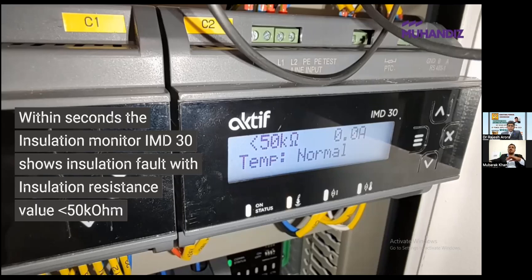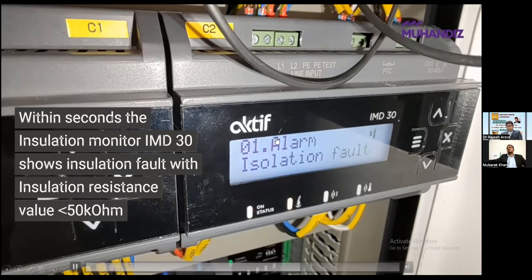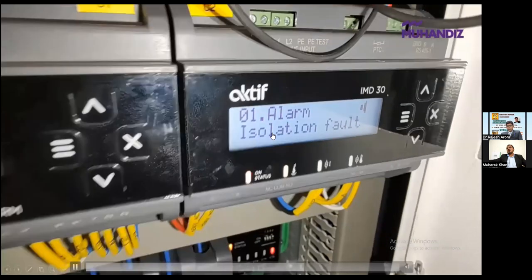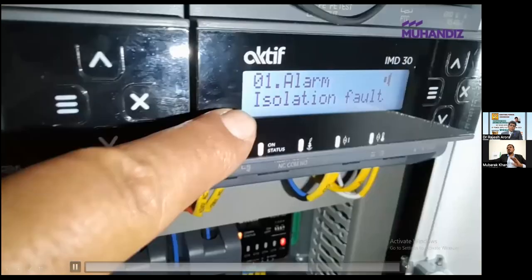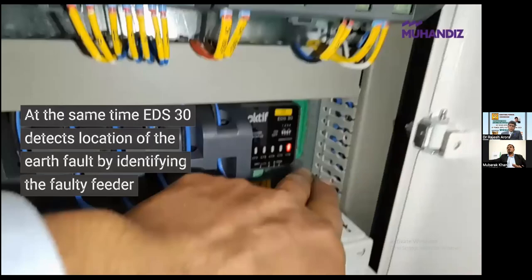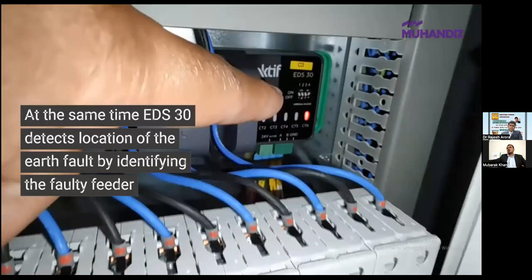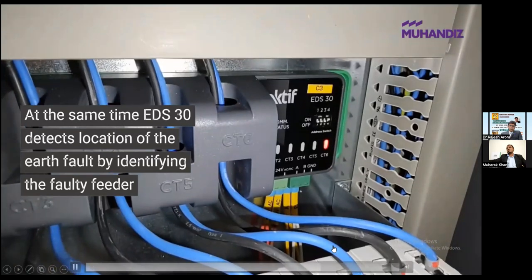But here you can see we have comfortably done it without any problem. We are 200% sure there will not be any leakage, any current flowing there. Got the point? So this is also a demonstration of how the IT system prevents any leakage current from phase to ground in case of a first fault. It has shown an alarm. Okay, one alarm is showing there. It is only showing an alarm. There is no tripping, no fire, no heating, no leakage current. And this EDS 30 has detected that this particular feeder has caused the problem.